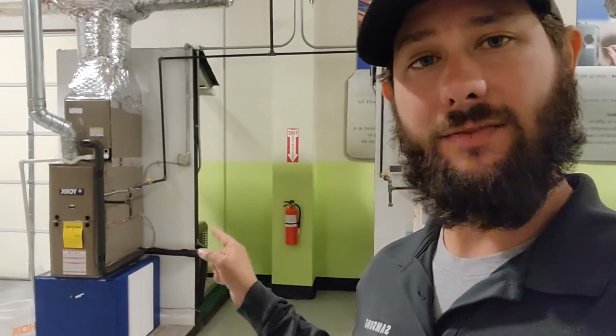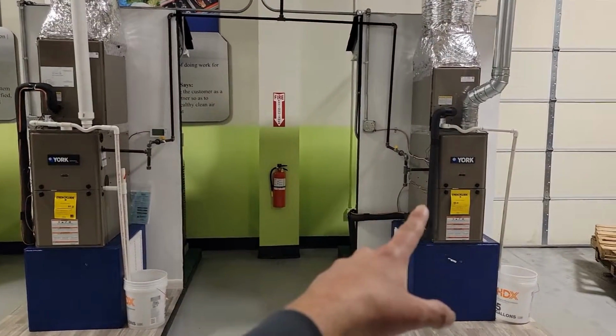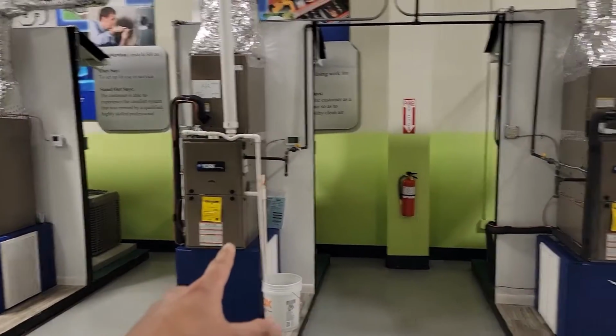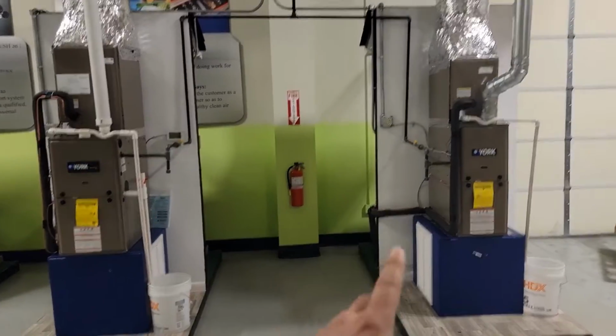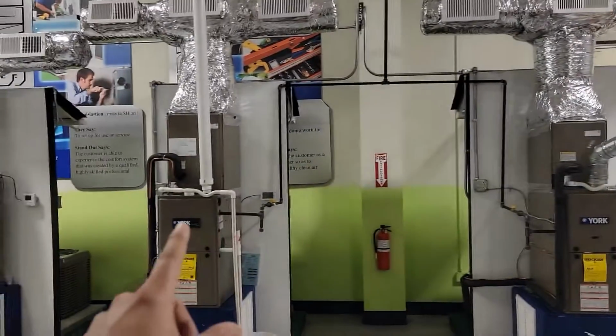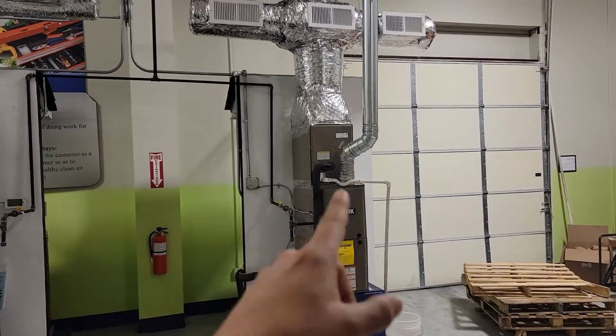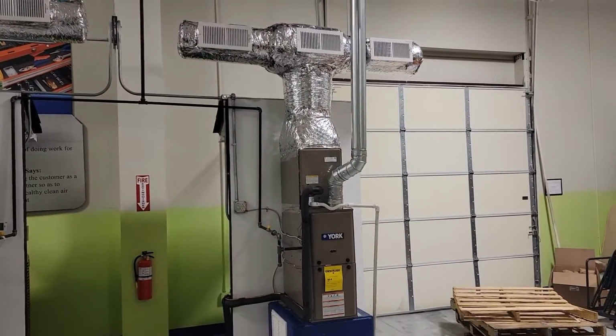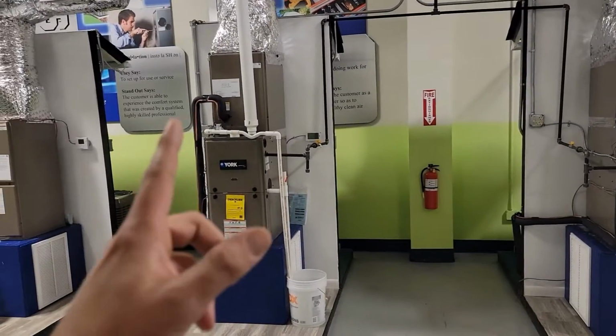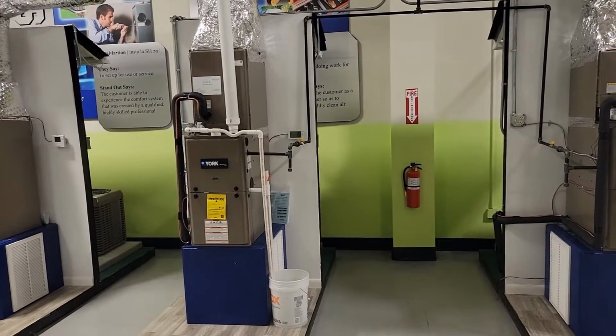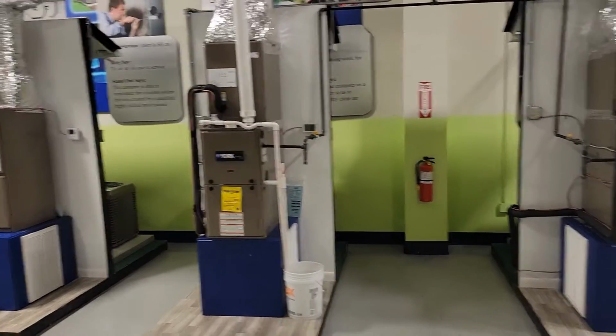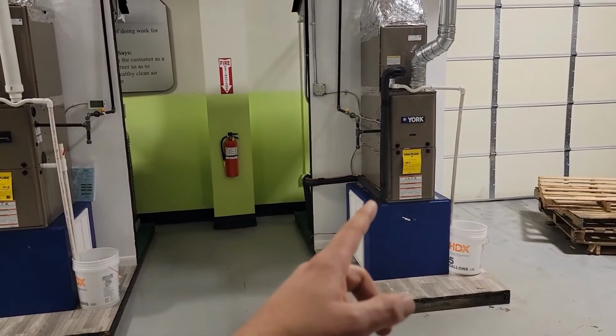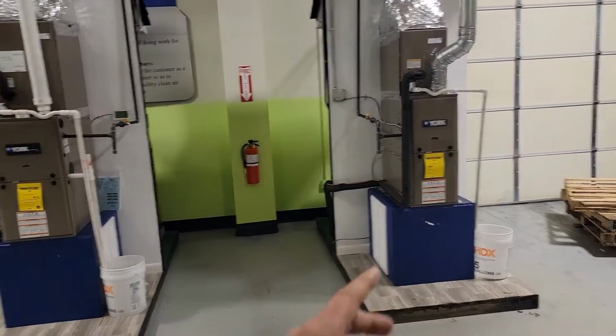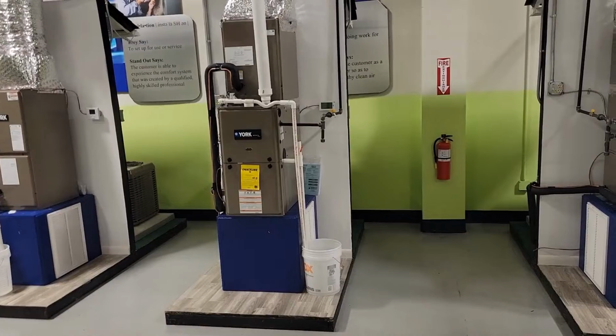You're watching HVAC Tips for Technicians. I'm Tad, and I'll be giving you the difference between 80% and 90% furnaces. So this right here is an 80% furnace, and this is a 90% furnace. The first obvious characteristic is the vent. The vent or the flue pipe for the 80% furnace is metal, and that is double wall piping. And then the vent for the 90% furnace is PVC. The reason is because this 80% is a non-condensing furnace, and this 90% is a condensing furnace.